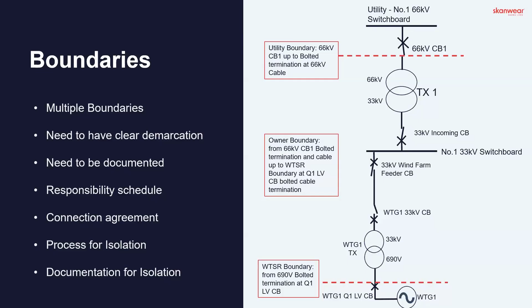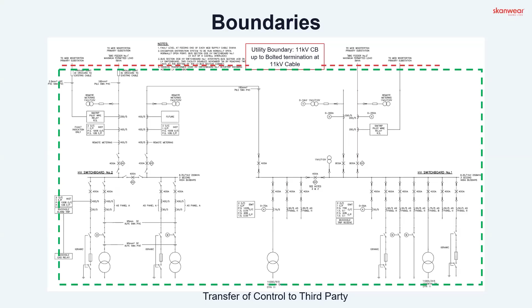Another example of a boundary, here's just a general site where typically, again, we've got the connection agreement with the utility provider. So at the 11 kV circuit breaker, the bolted termination, that cable and everything downstream belongs to the client. In this example, the client doesn't have any authorized persons or senior authorized persons, so they utilize a process to transfer the network over to an HV or MV maintenance provider that has suitable authorized persons and senior authorized persons to operate, control, and maintain that network. So they'll use a transfer of control as a third party. This transfer of control process needs to be clear, and it's a transfer of control from the owner across to the third party provider.